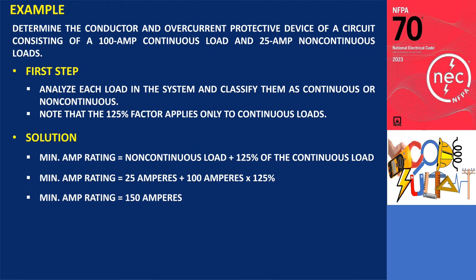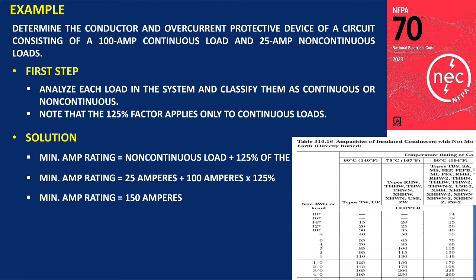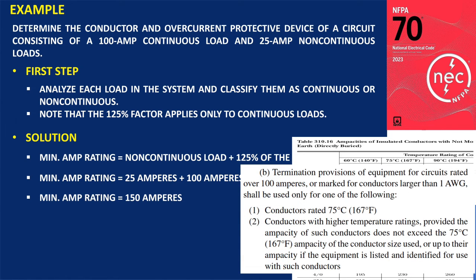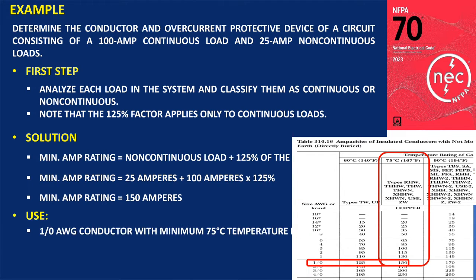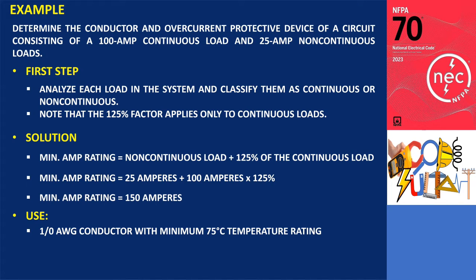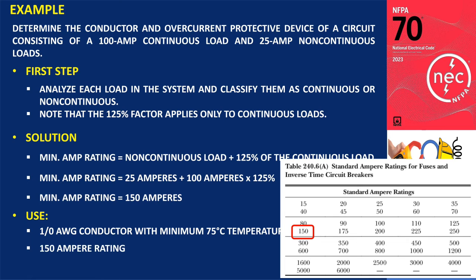Article 310 of the NEC provides guidelines for conductor selection, specifically Table 310.16 of NEC 2023. Since the total current exceeds 100A, and per Section 110.14C1B on equipment terminal rating, we base conductor size selection on the 75°C column of Table 310.16. Consequently, the appropriate conductor size is determined to be 1-0 AWG. For overcurrent protection, consulting Table 240.6A indicates a suitable device rating of 150A.